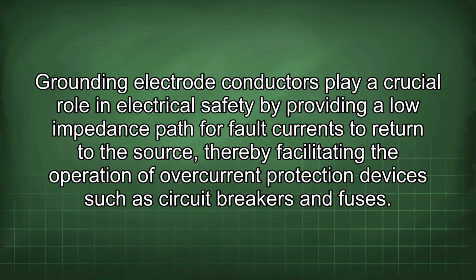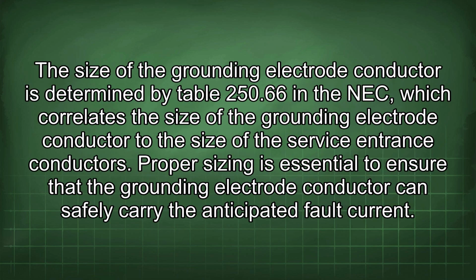Grounding electrode conductors play a crucial role in electrical safety by providing a low impedance path for fault currents to return to the source, thereby facilitating the operation of overcurrent protection devices such as circuit breakers and fuses. The size of the grounding electrode conductor is determined by Table 250.66 in the NEC, which correlates the size of the grounding electrode conductor to the size of the service entrance conductors. Proper sizing is essential to ensure that the grounding electrode conductor can safely carry the anticipated fault current.